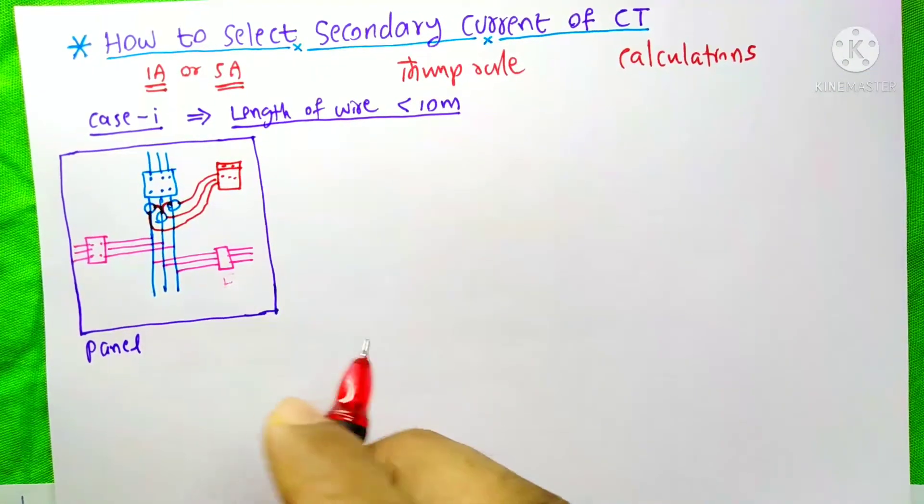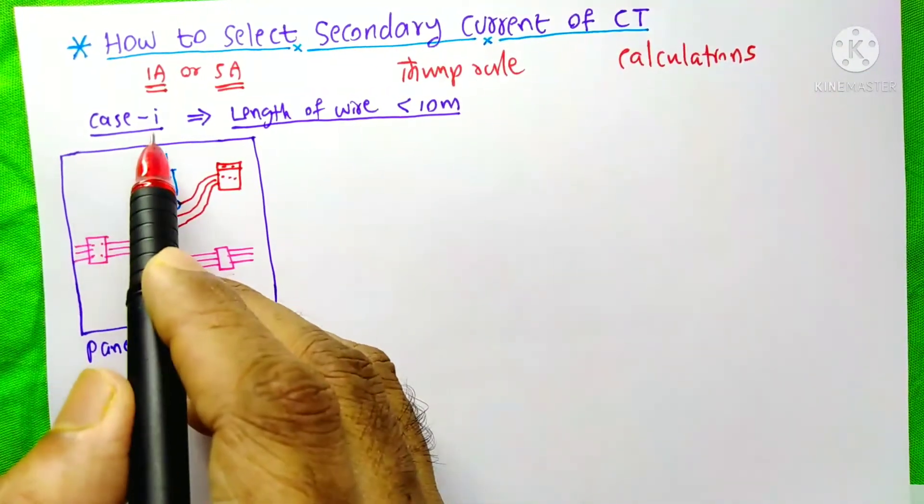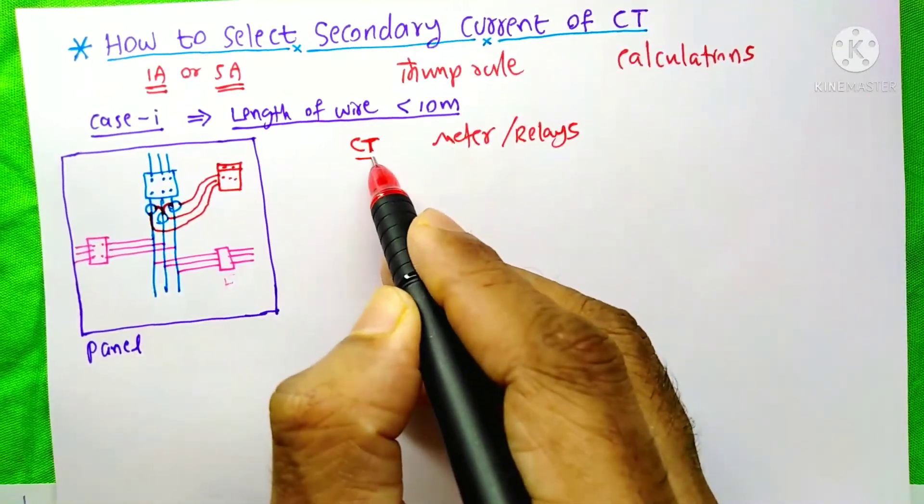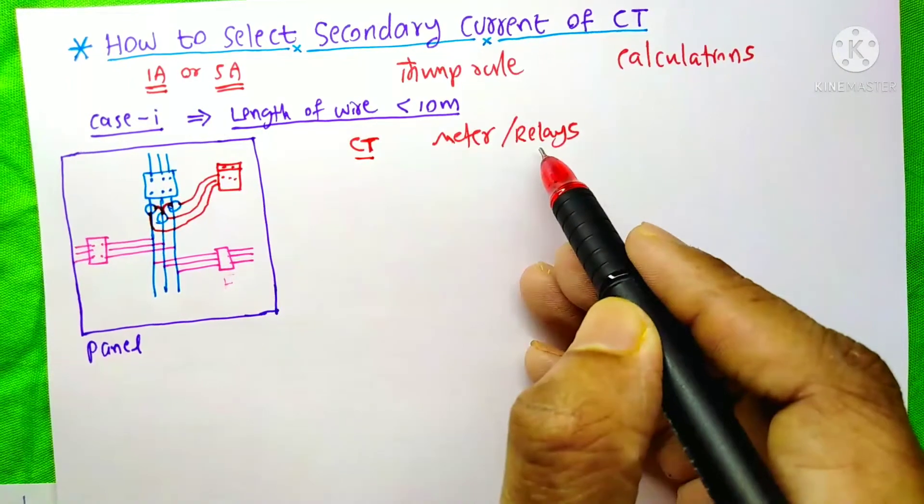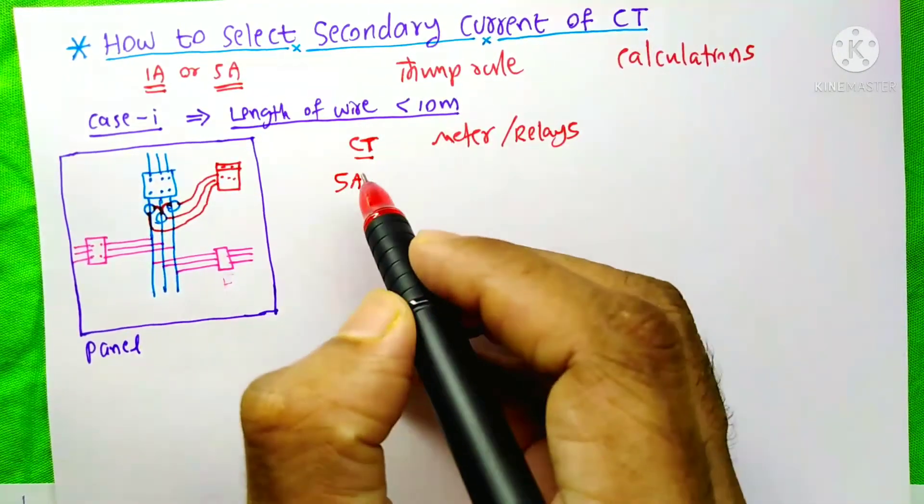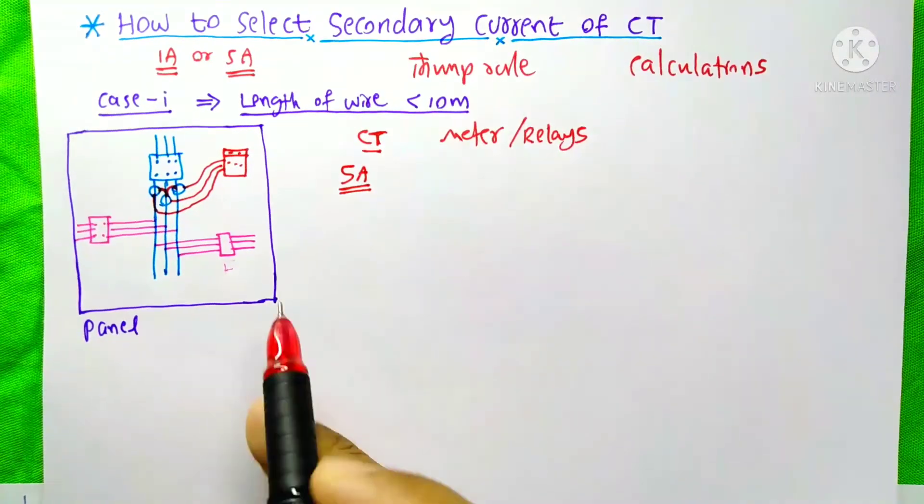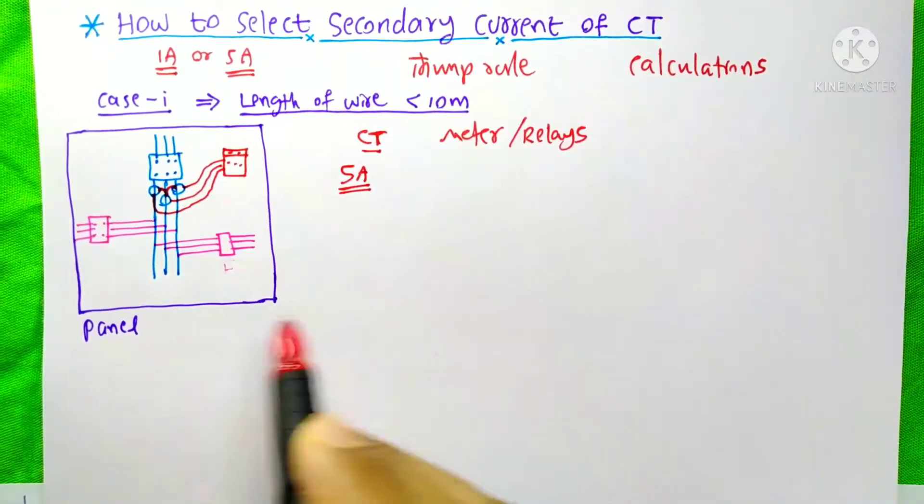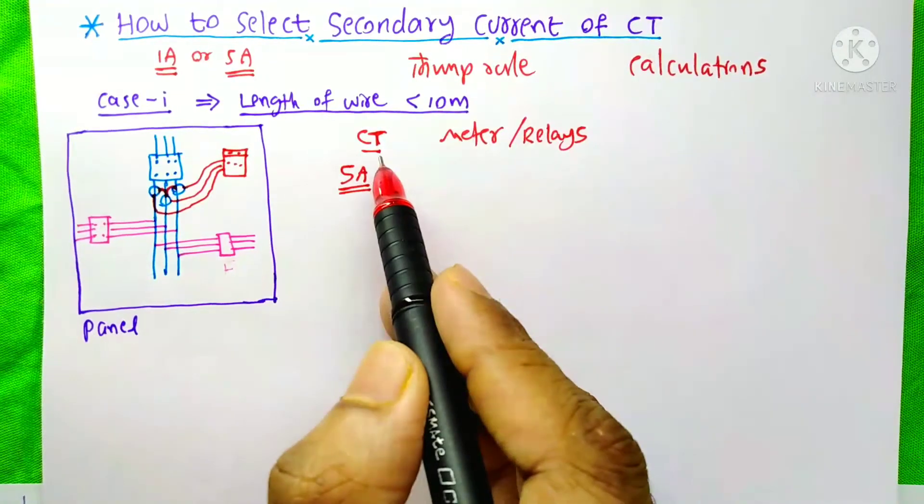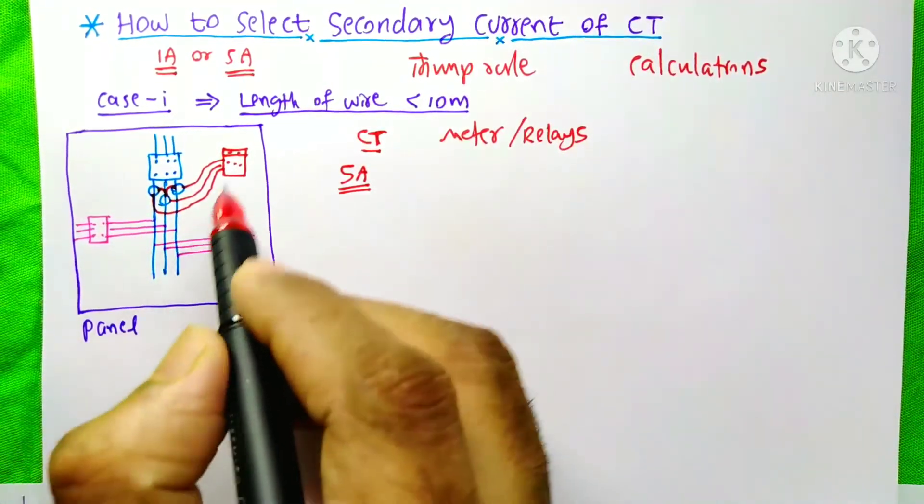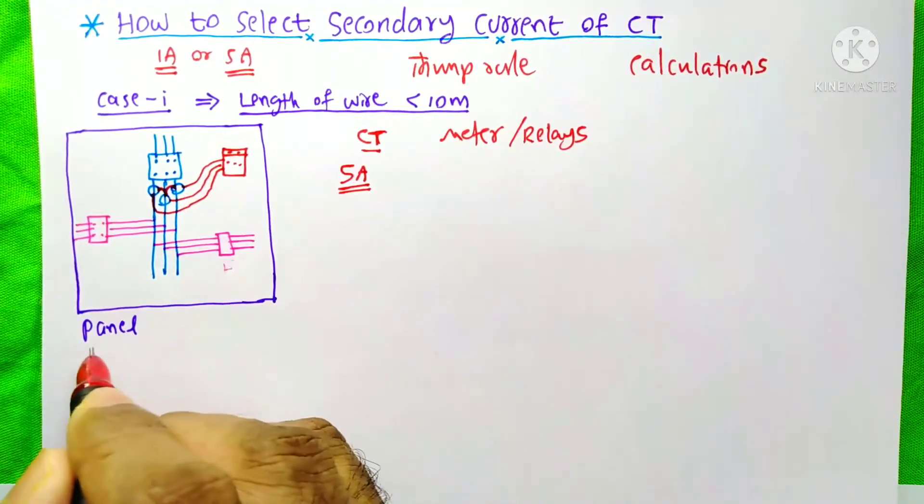Here are two cases. The first case is: if the length of the wire between CT and meter or relay is less than 10 meters, then we will use a CT with 5A secondary current. This case happens when both the current transformer and meter or relay are present on the same electrical panel.